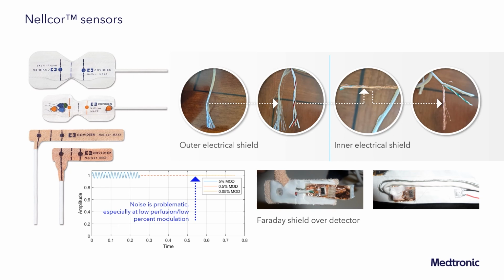And so here we can see that it is this piece of copper that folds over our detector when in use. And in this situation, when this is folded over, we have 100% coverage, or maximum coverage, of electrical noise on inner cabling and on our signals that we're trying to measure. And it's in this way that Nellcor is able to go all the way down to 0.03% modulation.